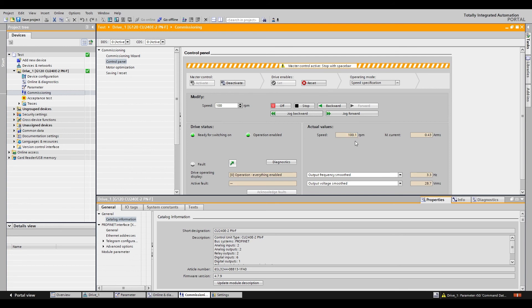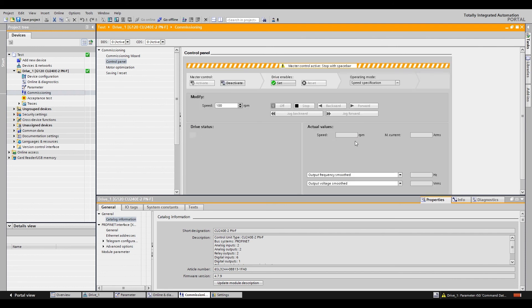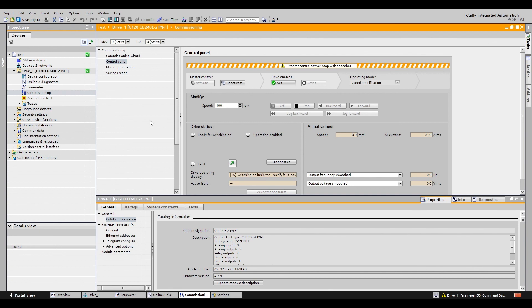Now to test the e-stop you can hit your button that's wired to digital input 4 and 5 and you can see that the drive has stopped. And now you have verified that everything's working properly. That is all you need to do for the safety commissioning for the G120.